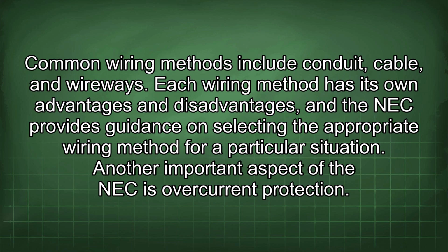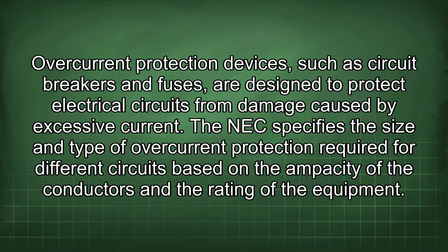Another important aspect of the NEC is overcurrent protection. Overcurrent protection devices, such as circuit breakers and fuses, are designed to protect electrical circuits from damage caused by excessive current. The NEC specifies the size and type of overcurrent protection required for different circuits based on the ampacity of the conductors and the rating of the equipment.